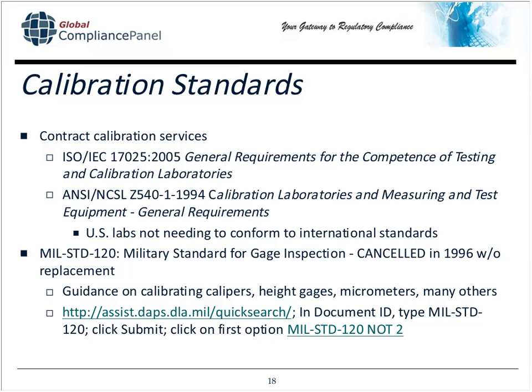I've given you the web citations to go look at this. It was very helpful. You may find it helpful also in developing your own internal procedures on how to calibrate calipers. I've been involved in usually notified body audits more than FDA inspections, where I've been asked, how do I calibrate my calipers? Fortunately, I've had specific documents in place that explain how I'm calibrating my calipers. If you send your calipers out, for example, it's up to your calibration firm to provide you with instructions on how they calibrate, and most will. If you calibrate things in-house using physical calibration standards, then you're going to have to provide your own equipment.